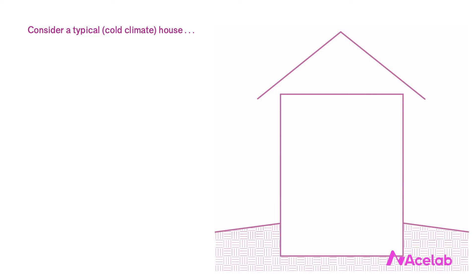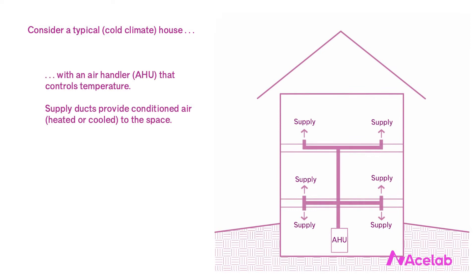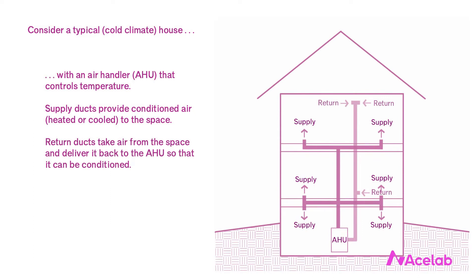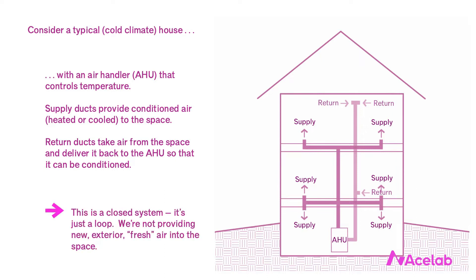Let's take a look at a typical cold climate house with a basement and two stories above grade. It has an air handler that controls temperature. Supply ducts provide conditioned air — either heated or cooled — to the space inside, and return ducts take air from the space and deliver it back to the air handler so that it can be conditioned. What we have is a closed system — just a loop. We're not providing new exterior fresh air into the space; we're just heating or cooling what's already there.